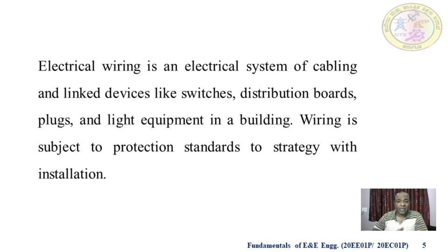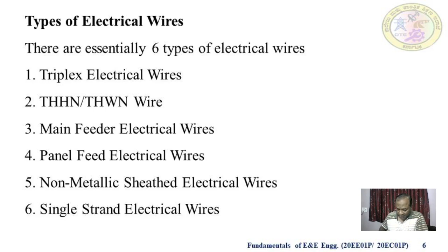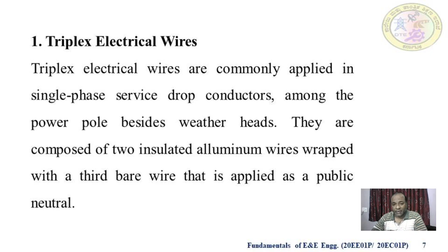Second one, THHN or THWN wire. Third one, main feeder electrical wires. Fourth, panel feeder electrical wires. Non-metallic sheathed electrical wires. Single strand electrical wires. We will study them one by one in detail. Triplex electrical wires. Triplex electrical wires are commonly applied in single phase service drop conductors from the power pole to the weatherheads. They are composed of 2 insulated aluminum wires wrapped with a third bare wire that is applied as a public neutral.